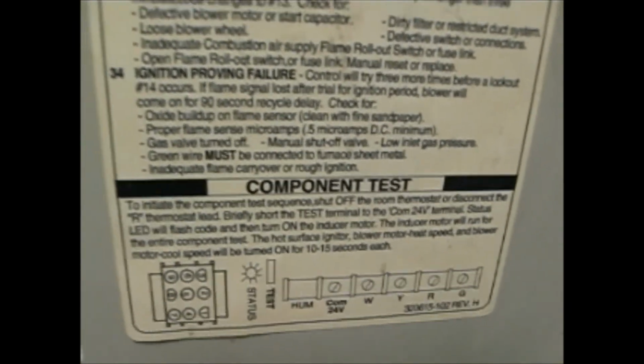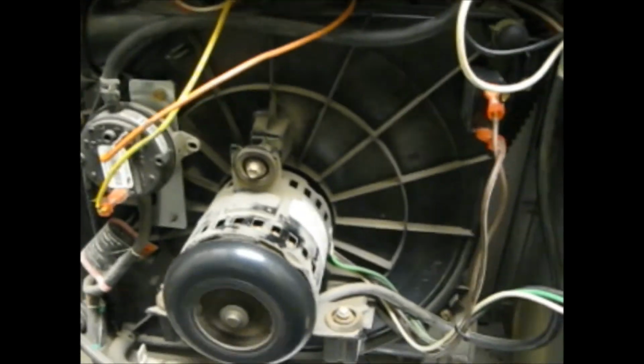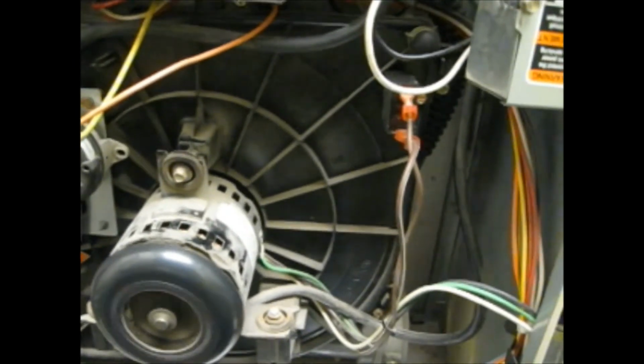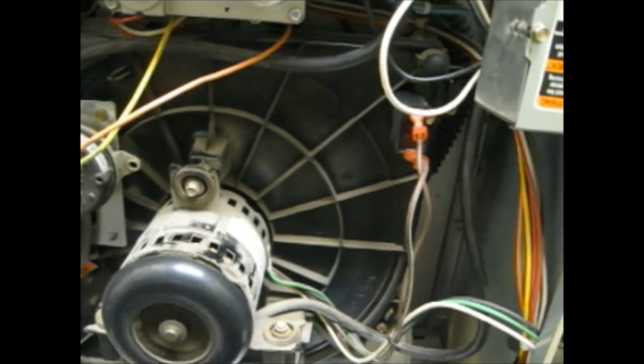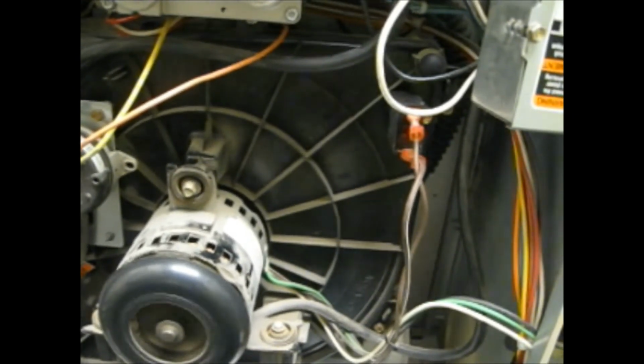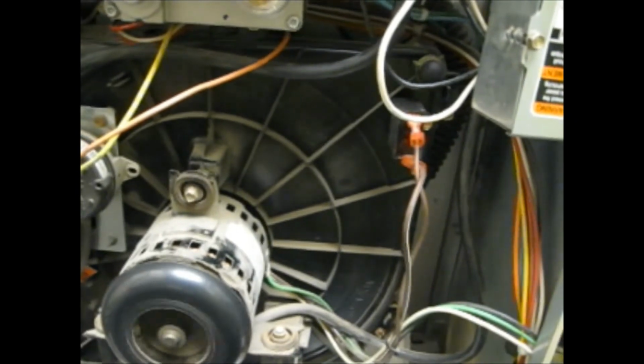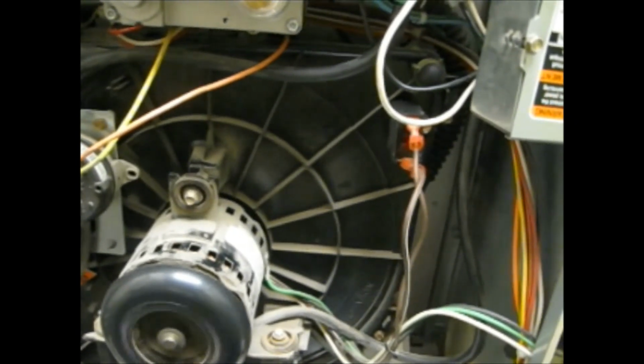Okay, remember our disconnected hot surface igniter? That's giving us a code of 34. 1, 2, 3. 1, 2, 3, 4. If we go over here, ignition proving failure. So that gives you a hint on what to look for. Now a lot of times when you have an error code, the system will attempt to light the furnace 3 times or so, and after the 3rd time it'll just go ahead and shut down and generate the code.